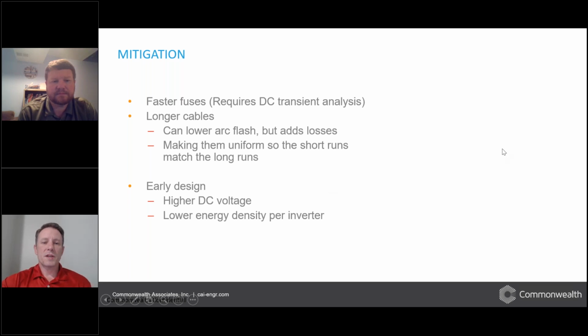So for mitigation for some of those high arc flash values, we can use faster DC or faster fuses for both the DC and the AC side. For DC, sometimes we need to do a transient analysis to see if they're actually faster and decide what to do about them, because we use steady state fault currents for the normal analysis.